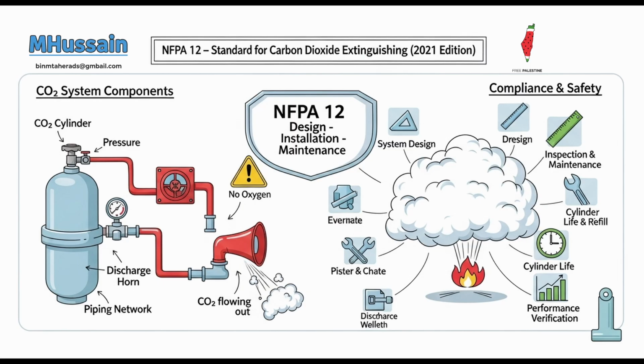You mentioned equipment shutdown. An absolutely crucial aspect is equipment shutdown. If the continuing operation of equipment associated with a hazard could sustain the fire, for example, a fuel pump feeding flammable liquid to a burning area, its power or fuel sources must be automatically shut off as an integral part of the system's operation. Cut the fuel. Cut the power to the burning thing. Exactly. This prevents the fire from being continuously fed, giving the CO2 the best chance to extinguish it. The only exception noted is for lubricating oil systems associated with very large rotating equipment, like massive turbines. Steam turbines are different. In these cases, an extended CO2 discharge is provided to cool the equipment down gradually over time, as a rapid, abrupt shutdown could potentially be more damaging to the machinery than helpful in the fire scenario. Gentle shutdown for big machines.